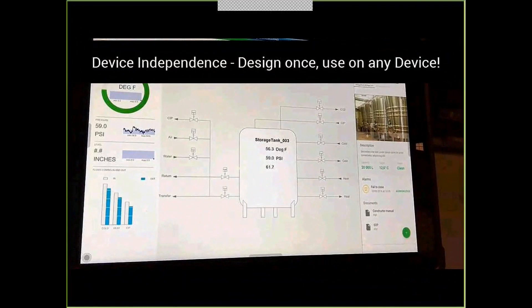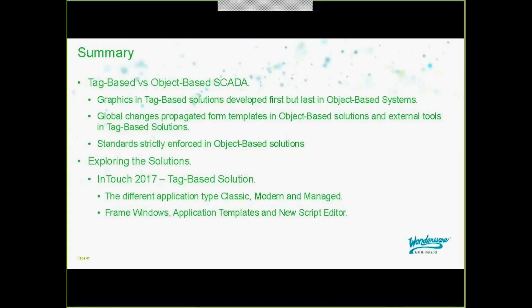To summarize: we talked about tag-based versus object-based SCADA. In tag-based solutions, graphics are developed first; in object-based solutions, graphics are developed last. Global changes are propagated from templates in object-based solutions, while external tools are used in tag-based solutions. Standards can be strictly enforced in object-based solutions, but it's much more difficult in a tag-based solution.